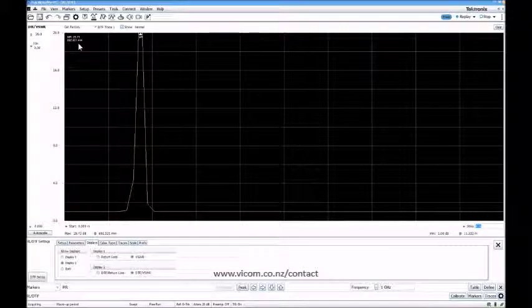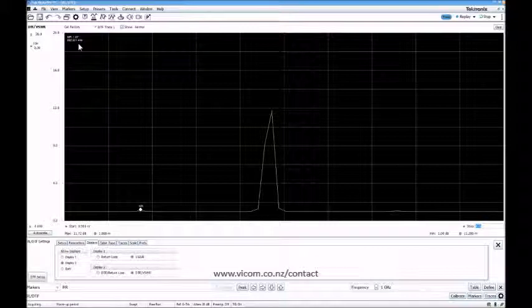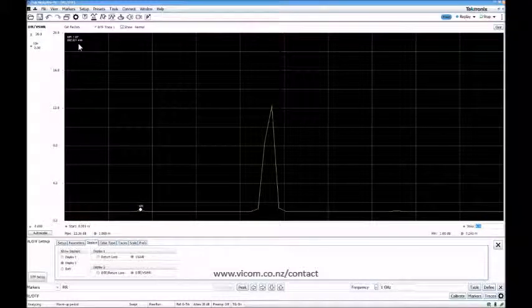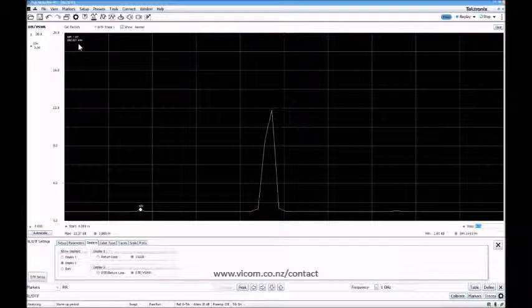And then I add this one. So just adding a cable to it. I don't think there's too much to it. It's very simple measurements you can do. But this is making sure that you can do the distance to fault measurement. You can see if there's a cable that is on its way of breaking or broke.